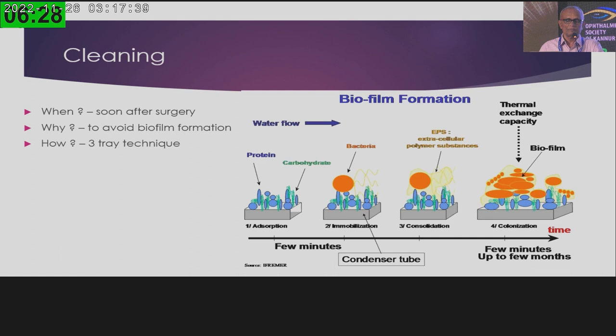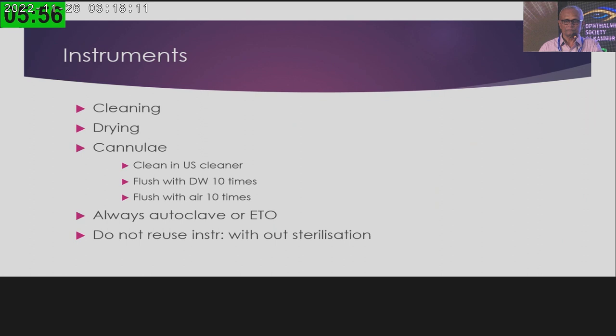Biofilm formation has different stages. In the earliest stages, within minutes, you can clean and eliminate organisms. Otherwise, bacteria become adherent, accumulate extracellular polymer substances, and the biofilm becomes very hard and gets lodged in the instruments. For a cannulated instrument, it is very difficult to dislodge biofilm once it has formed inside.